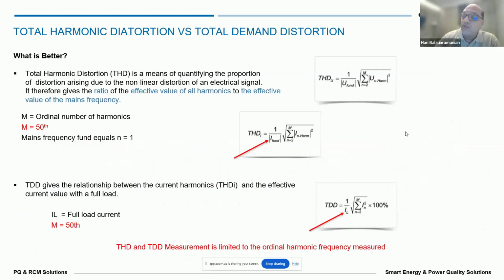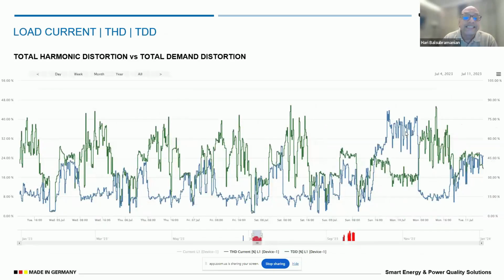Say, for example, you have a device which calculates THD and it only finds harmonics up to the 15th harmonic, which means the device should naturally be considering only up to the 15th harmonic for THD calculation. This is a very important point which we need to understand. So while we measure the harmonics and THD, we need to know up to what harmonic order the device measures, and then how the THD and TDD are calculated. So this is about THD and TDD for us to understand.